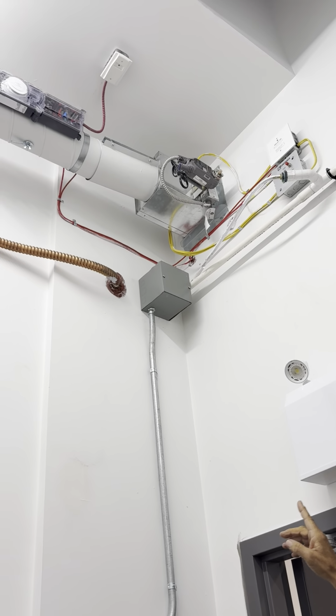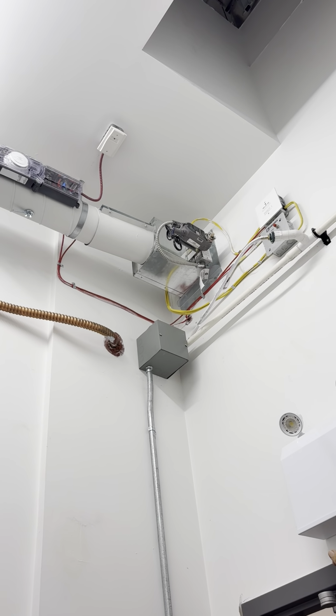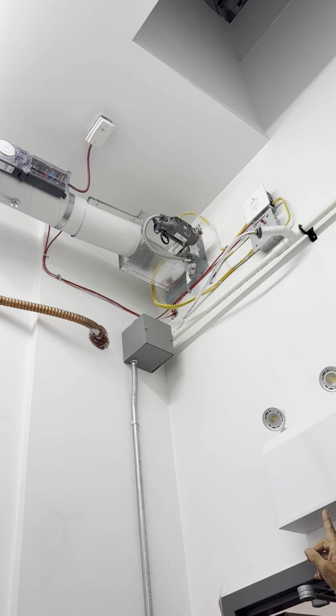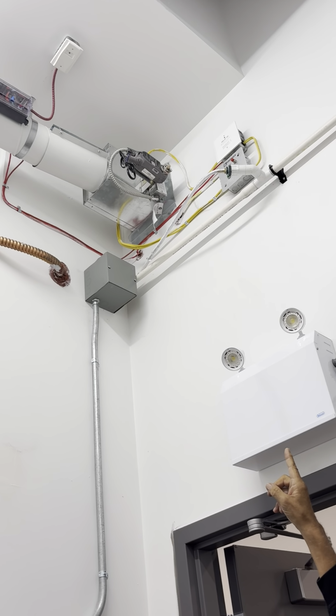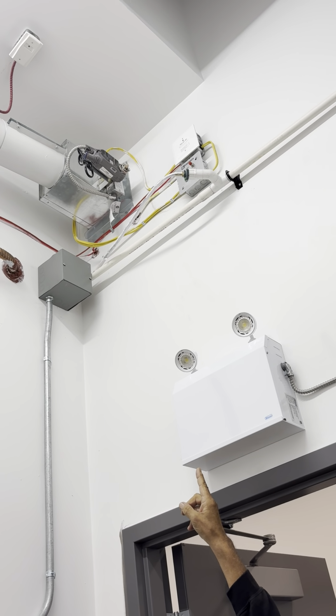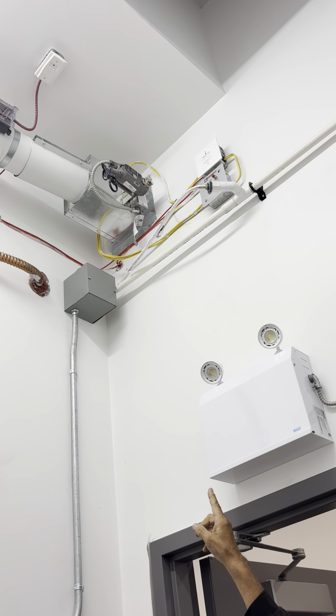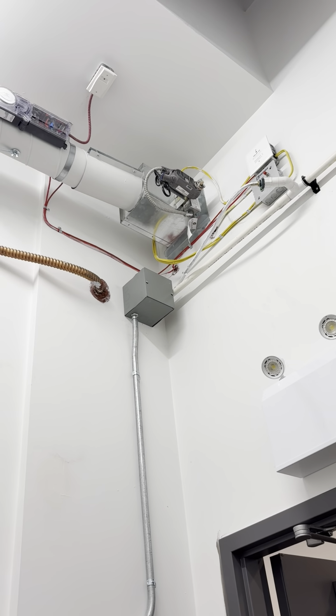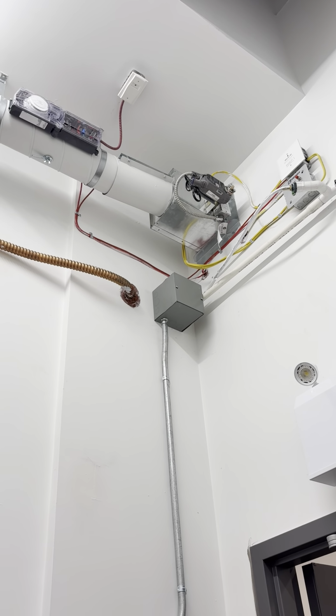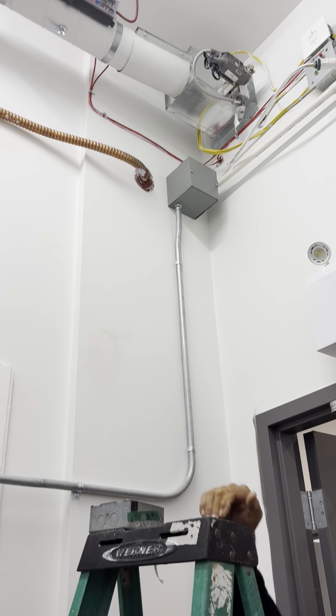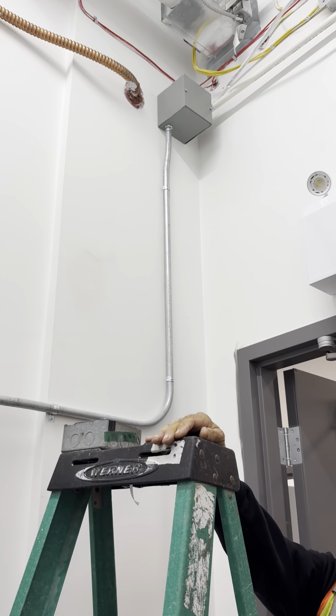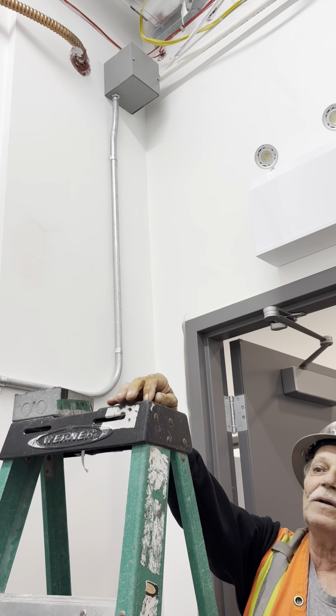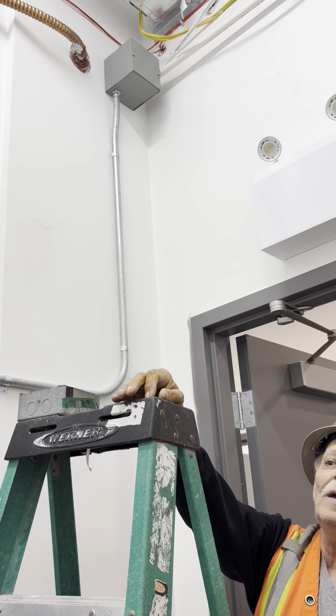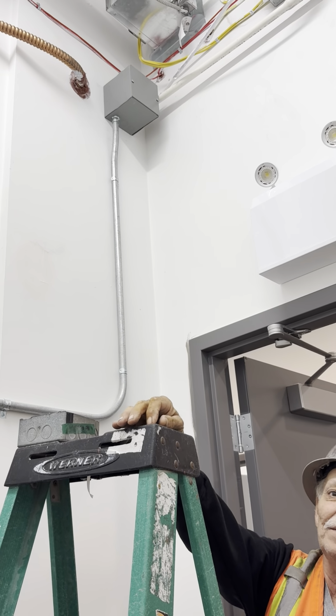Okay, it stays closed until there's a button pressed on the side of this black box. Did you see the small junction box beside the motor? There's a button on it, that's where you reset it. It resets, goes back to the normally open position, and stays there until the next fire alarm sets it off. Oh, so we have to manually reset it once it triggers? Yes. It also works on heat, so if the heat gets up to fire temperature 165, it also sets it off.